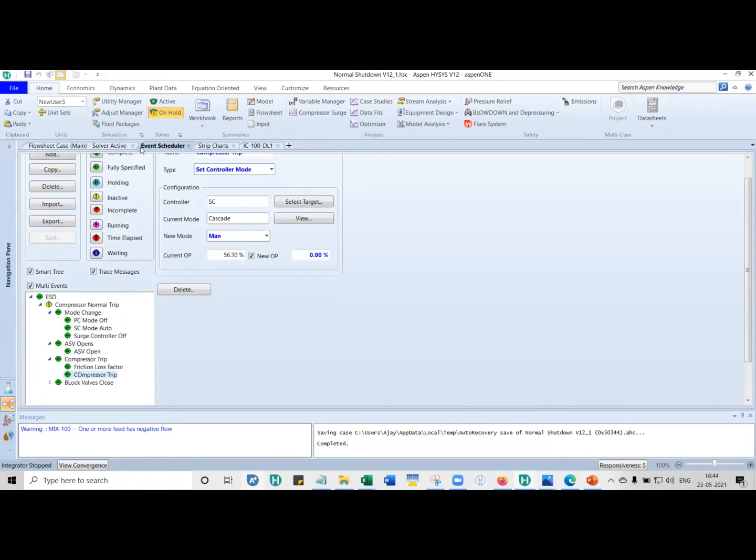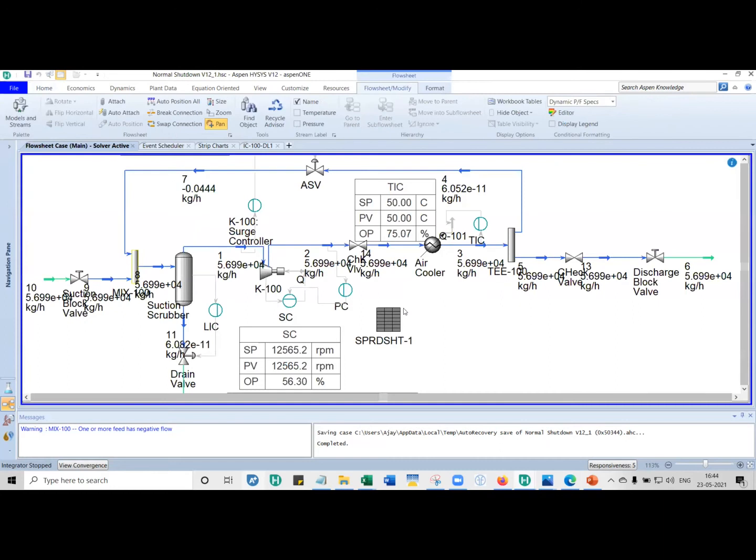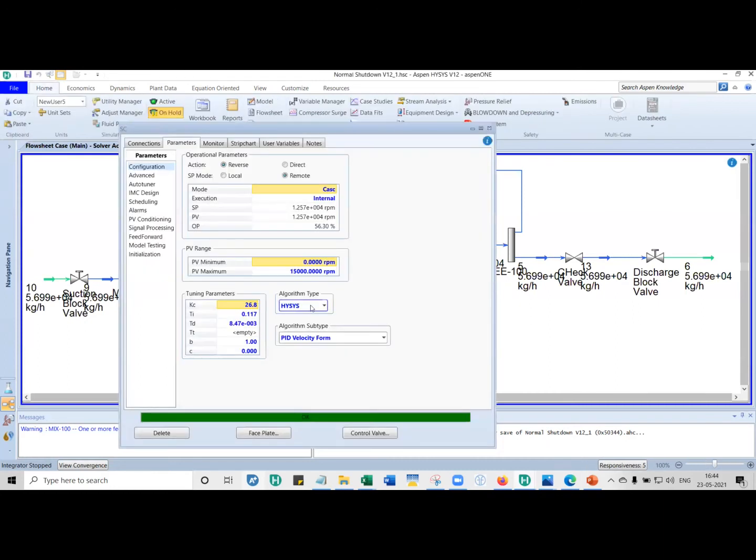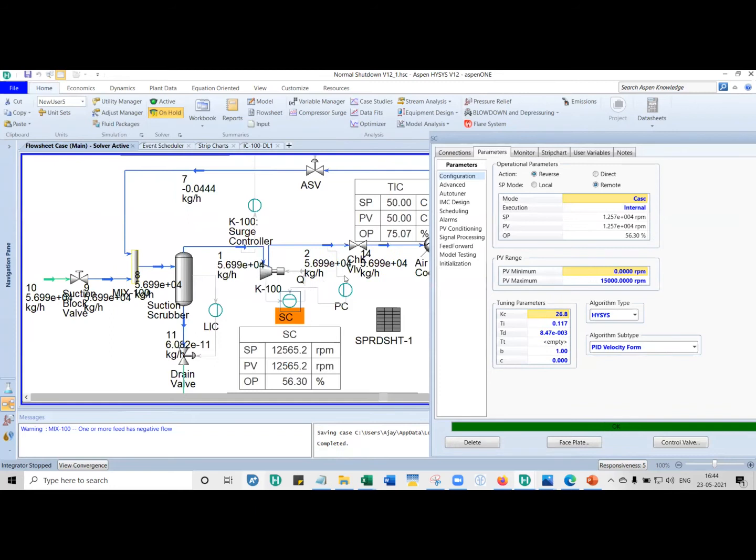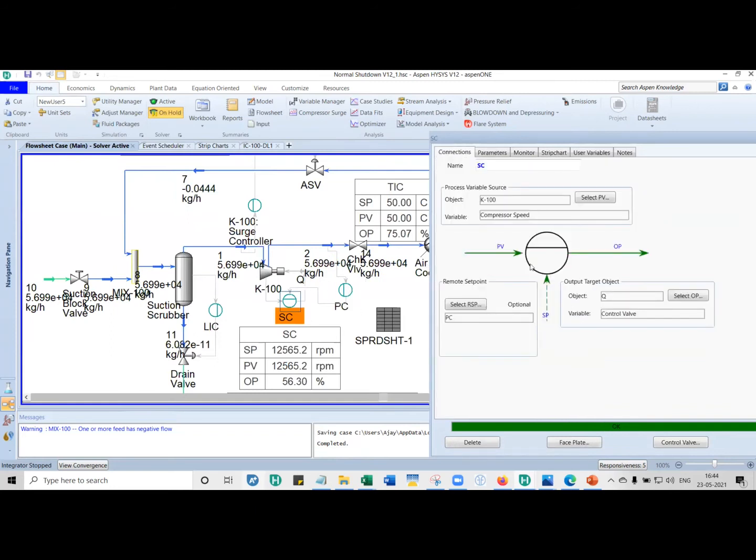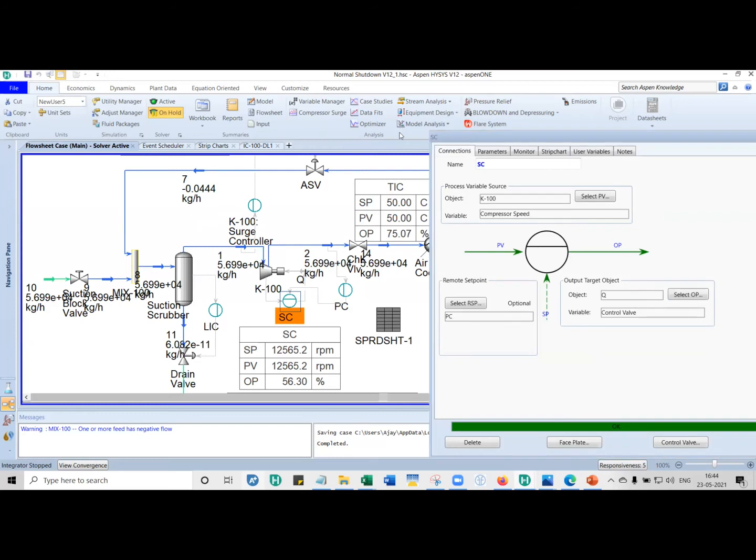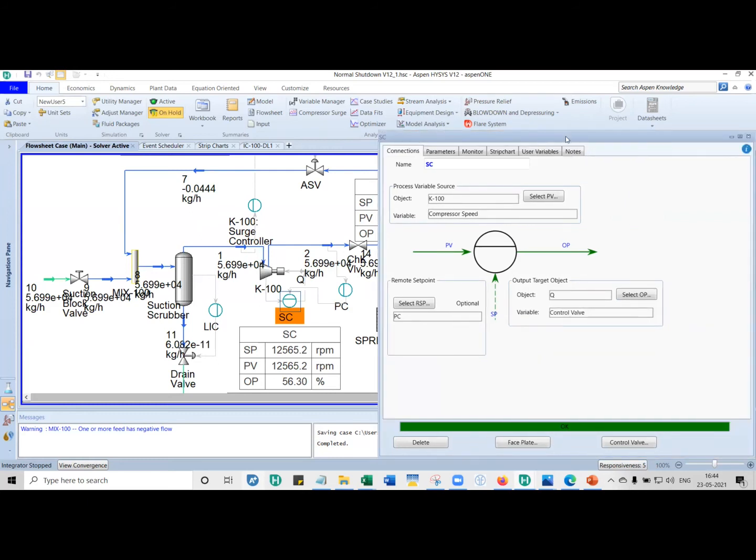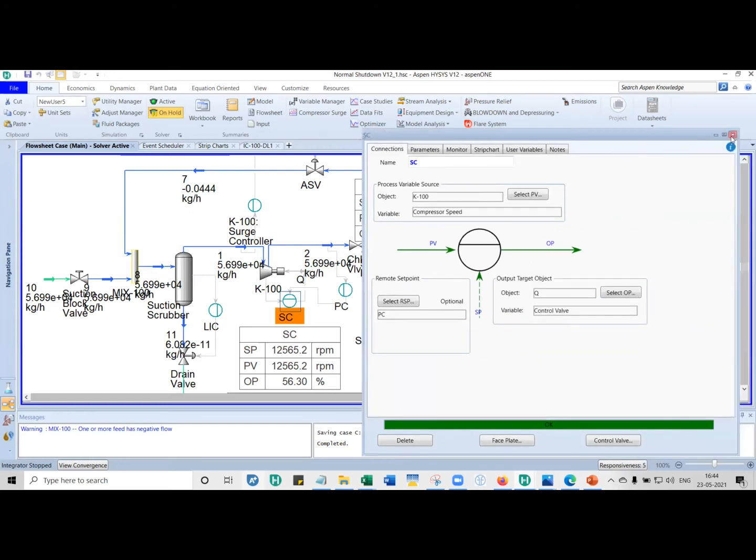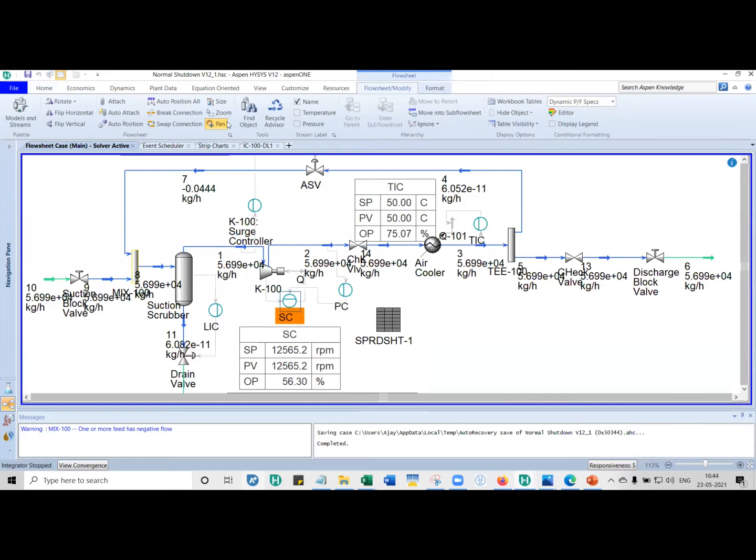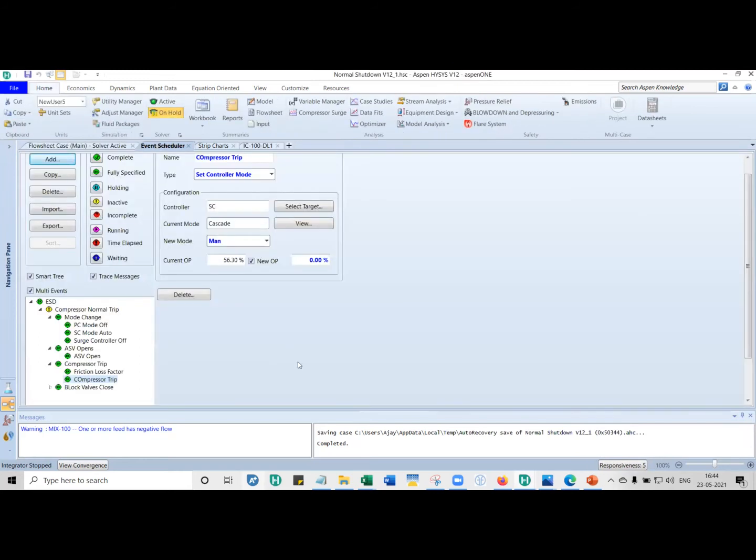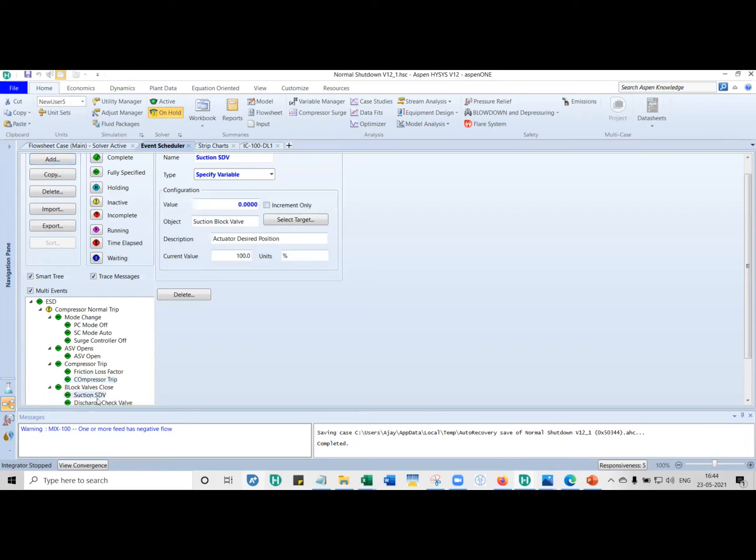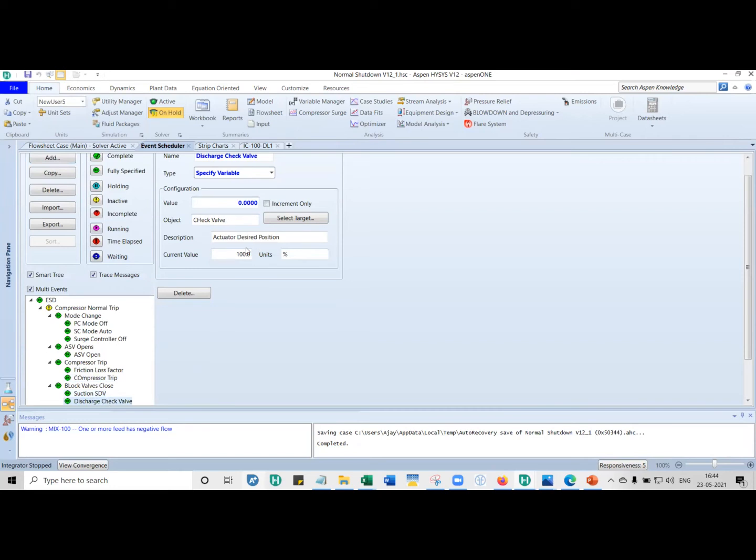Because it's a cascaded controller, if you look at SC, this is taking a signal from PC. The output of this PC becomes the set point of the speed controller. So we don't press zero on the OP to shut it off, whereas we are automating it here. And then we close the block valves, suction and discharge block valves. It is a shutdown. It is at 100, we want it to go to zero.